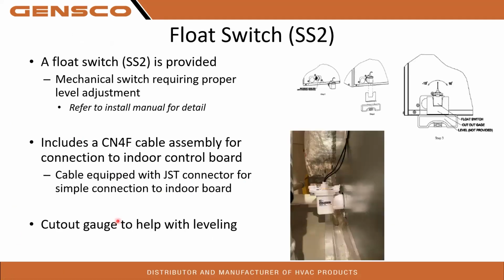Float switch. This is the float switch that comes in the kit. As you can see, it plumbs into the secondary port on your coil. This needs to be plus or minus 10 degrees from level. Most guys can eyeball that, but for the ones that cannot, I recommend using a level. That's not provided in the kit, but they do give this cute little cutout gauge to help with the leveling. Again, most people probably won't ever use that, but it's there if you need it.